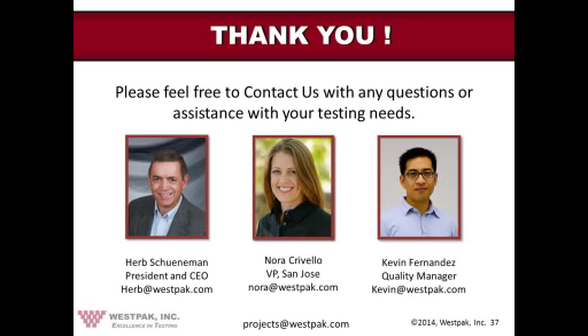I remember trying to accelerate the process of some stored food sometime, and it was a miserable failure. So you have to be pretty careful about the application of it. And in fact, the FDA is also pretty careful about it, because the standards that they use, ISO 11607, I believe, strongly recommend that you use accelerated aging in concert with real-time aging. What does that mean? That means that you have to keep checking to make sure that your 6-month, 12-month, 18-month, whatever that happens to be, accelerated and real-time aging results are virtually the same, very, very similar.